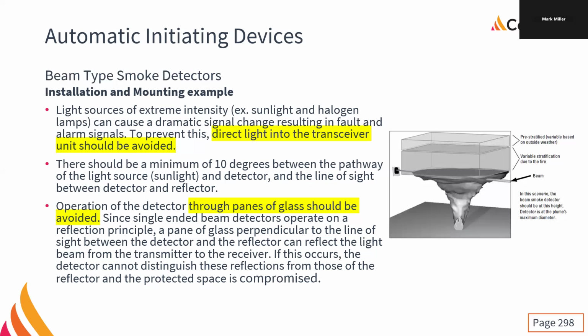Don't put them through glass. Yes, it can read through glass to a point, but we're working on the reflection principle with a single end beam detector, which is most of the time. And a pane of glass perpendicular to the line of sight is going to refract and reflect the light. Think back to physics, and it's going to cause issues. The beam detector is going to get confused, and it's going to start throwing troubles or random alarms.